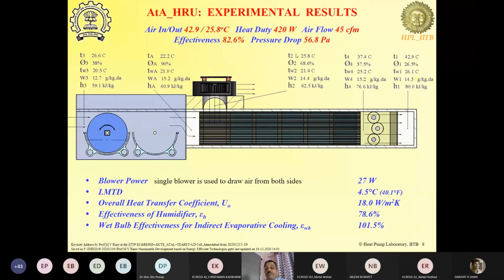So when you supply the fresh air, the same amount of fresh air which goes into the room is going to displace the same amount of stale air from the room, and that air from the room is going to be at the indoor condition. In this case, the indoor condition was about 26.6 degrees centigrade and 58% RH.